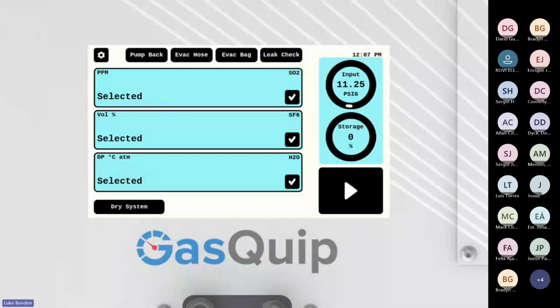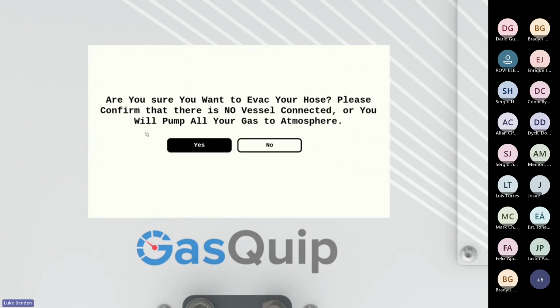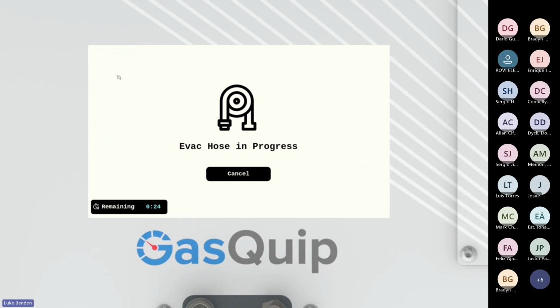What we're going to do first is pull an evacuation on that sample hose to remove any residual gas that we had from previous tests, or maybe there's some moisture in there that we need to pull out. So we'll run an evacuate hose function up here in the top left. It's going to say, are you sure you want to evacuate your hose? Please confirm that there is no vessel connected or you will pump all your gas to atmosphere. So we don't have anything connected yet. So we'll evacuate that hose.